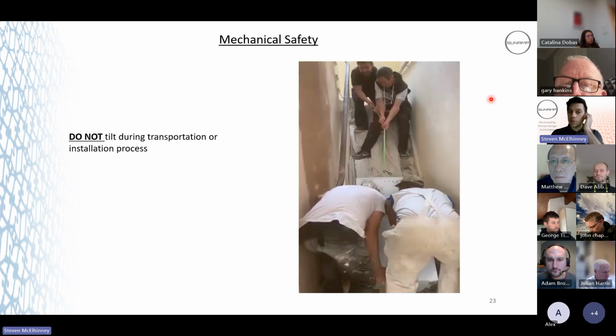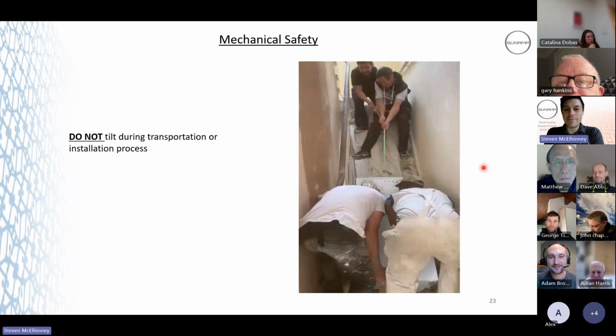Don't tilt the battery during the installation process. Obviously the plumbers, nobody's got any steel toe caps on, it's just ridiculous. The plumbers have got the painter and decorators involved in getting this battery up the stairs. What we do say is you shouldn't tip the battery more than 45 degrees, for two reasons. If there's any liquid phase change material inside the unit, it may tip out the breather cap, and that will alert somebody to thinking there's a fault. The other reason is if you tilt it more than 45 degrees, you might get overwhelmed by the weight, because they can be quite heavy.